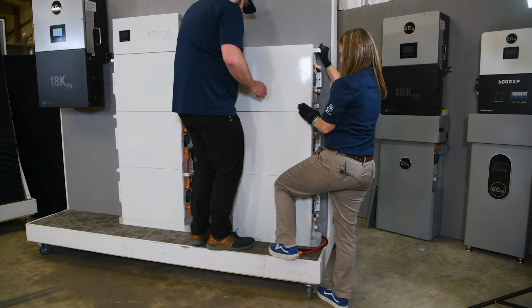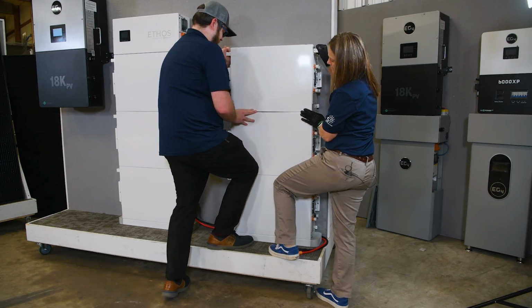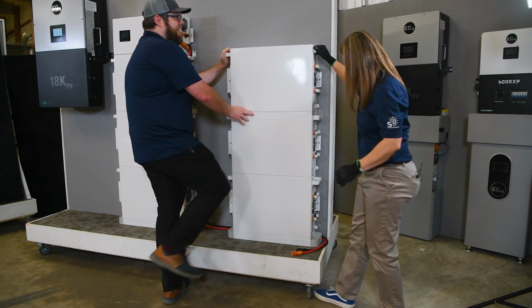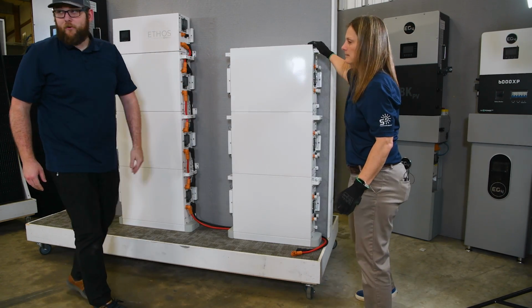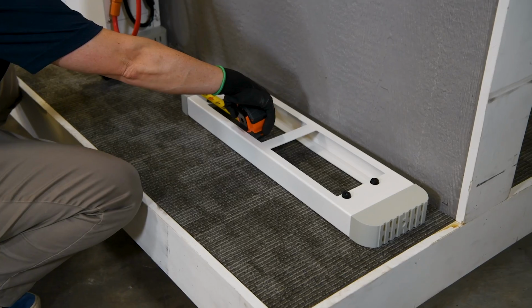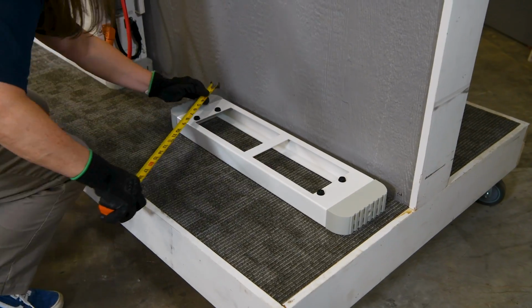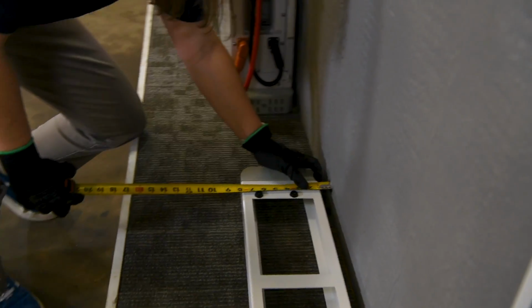Due to the constraints of our setup today, we'll ensure there's a 12-inch gap between our battery stacks, highlighting the importance of spacing for optimal cable management. This will demonstrate the ideal distance relative to cable lengths. However, please note that the inverter is positioned closer than recommended, at about half the advised distance, for the purposes of this demonstration. To make sure we have the appropriate spacing, I'll first measure 12 inches from the outside of my first base to the inside of the second base, leaving about a 1.2-inch gap from the wall.